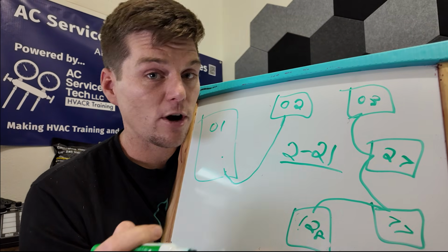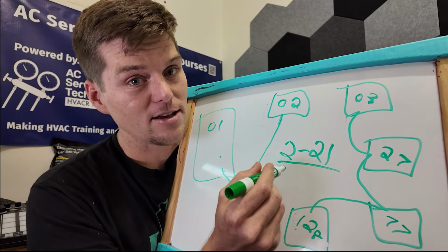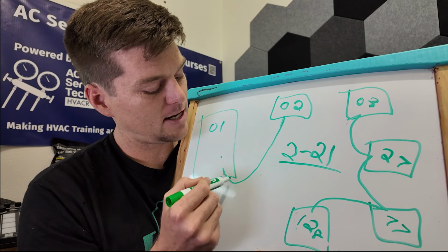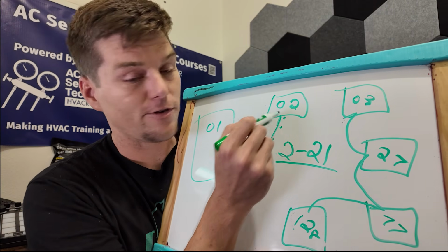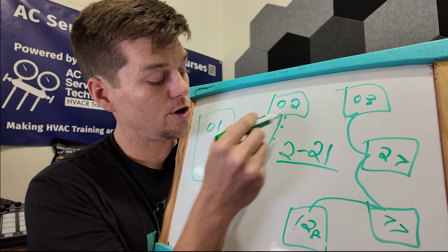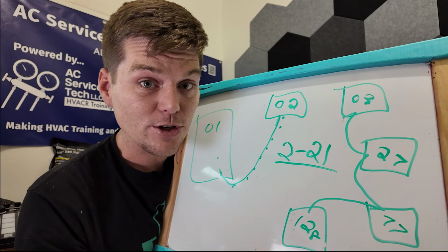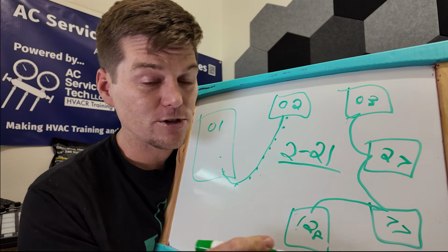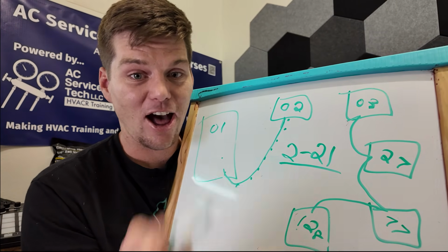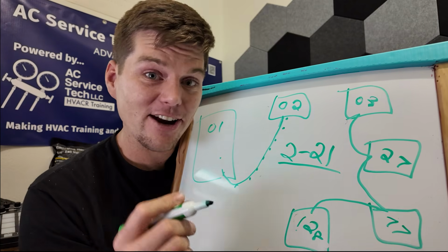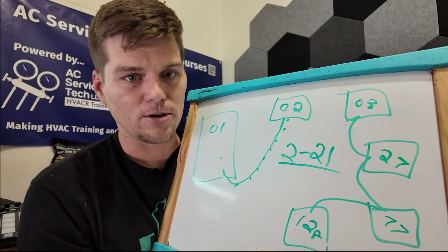And so we use this to our advantage, knowing what this setting does, to know that this is going to be sending data packets constantly to the first indoor unit. If this indoor unit sees this outdoor unit, what does it do? Well, it has an override force command to open expansion valves and lock thermostat and turn the green LED light on the controller.